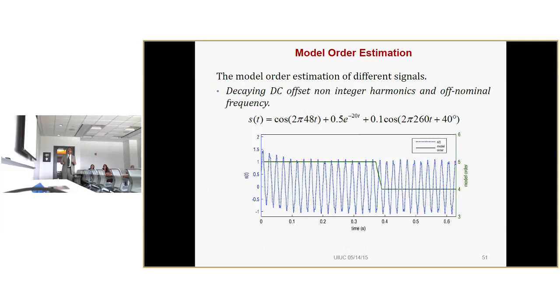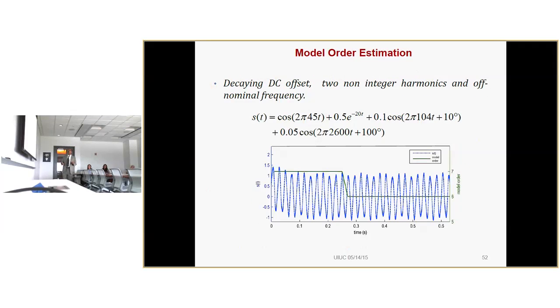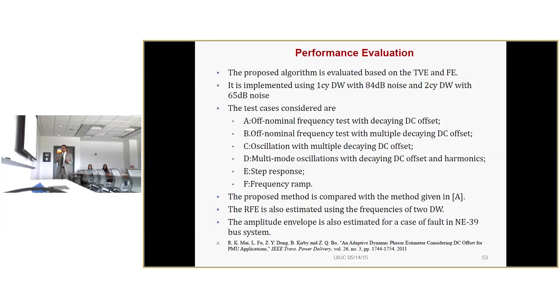If you see the signal, it contains fundamental, it contains DC offset, so third order, and these are the oscillations, which are another 2-5 order. Till the DC offset was there, it had given a 5 order model, and subsequently it converged to 4 order. So the method is actually very accurate in the order. This was non-integral harmonics. Again, initially it was 7th order, then came to 6th order after DC offset. And for various test cases which are given in the IEEE standard, we have verified the performance.